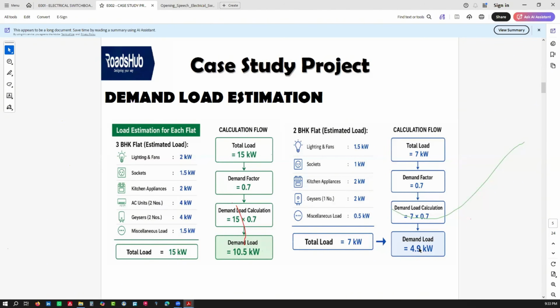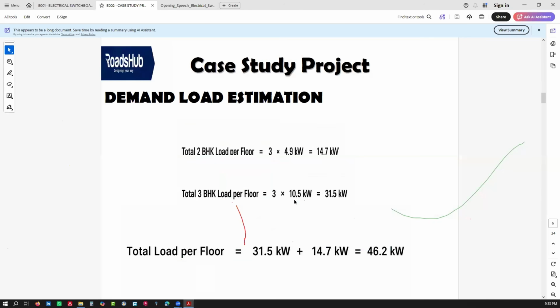So once you get the demand load estimation, you will actually have a value. The total number of 2 BHKs that you have per floor is 3. So 3 times 4.9, you get 14.7. And then you have 3 bedrooms, 3 of them. So times 10.5, you get 31.5. So add these 2, and you get the total load per floor.